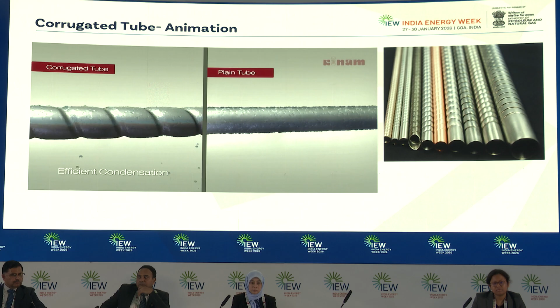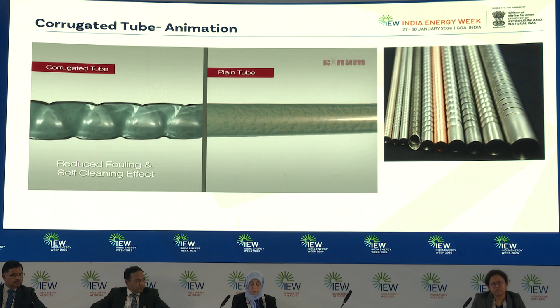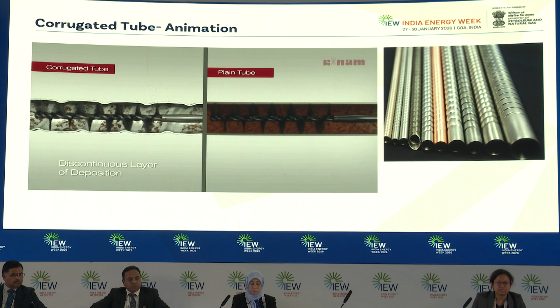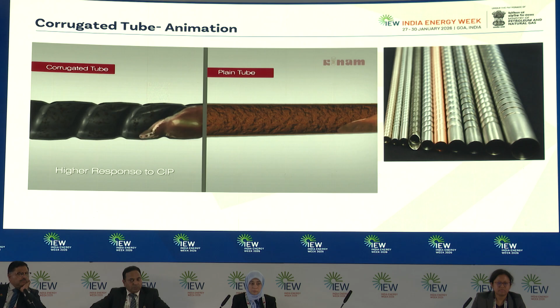Higher peripheral turbulence due to corrugations does not allow the suspended solids in the fluid to settle on the tubes, thus giving it a self-cleaning effect which results in reduced fouling. This ensures longer running time without stopping for cleaning. The response to CIP cleaning or mechanical cleaning by brush is better in comparison to a plain tube heat exchanger due to the discontinuous layer of deposition.